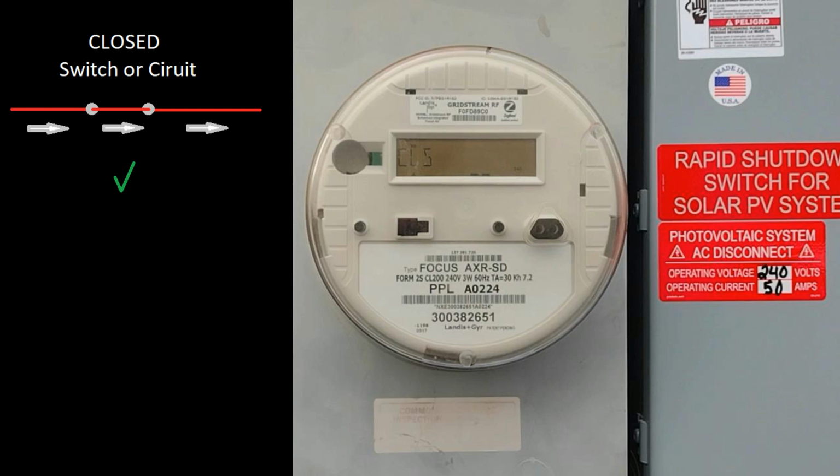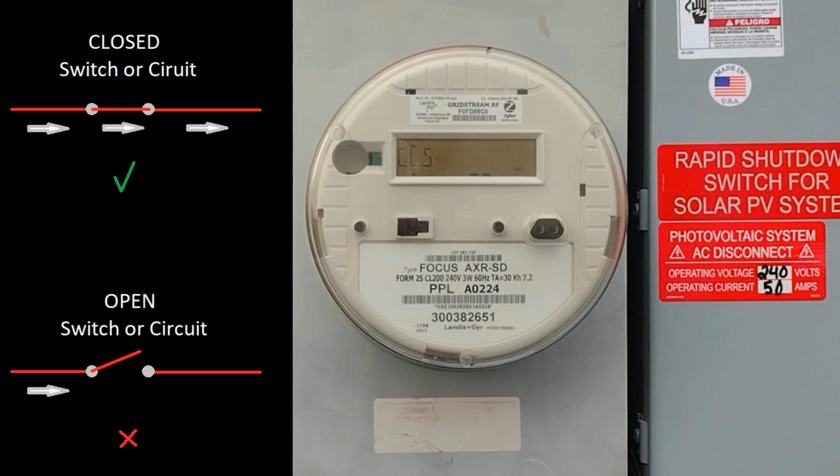It means that you're receiving power to your property, or if you're generating power back, it's flowing through the meter as it should. If it says OPN, OPN means that the meter itself is getting power on the PP&L side, but the bridge is open, the circuit is open, and no power is flowing through the meter. So that's going to indicate that there's either a fault inside the meter for some reason, or PP&L might have cut off your power and is not allowing power to go through.